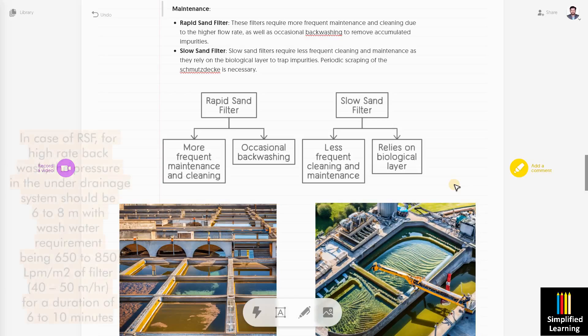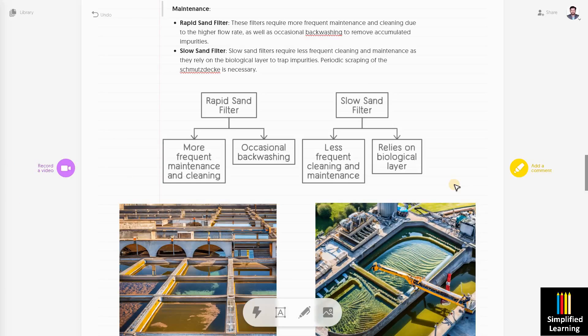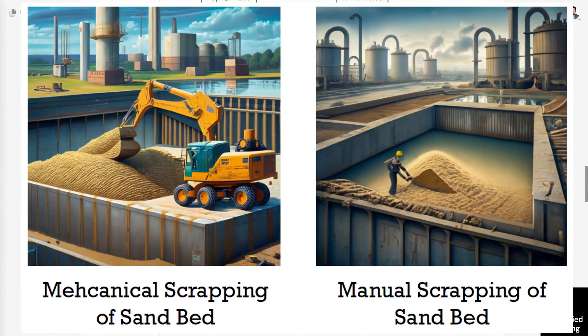In terms of maintenance, rapid sand filter requires frequent maintenance because high flow rates cause clogging of the filter bed very frequently. That's why backwashing every 24 to 48 hours is carried out, using the same filtered water. For slow sand filter, we periodically scrape the upper layers of the biofilm — the schmutzdecke — which forms on top of the filter bed. A total new layer is then laid over the filter bed.